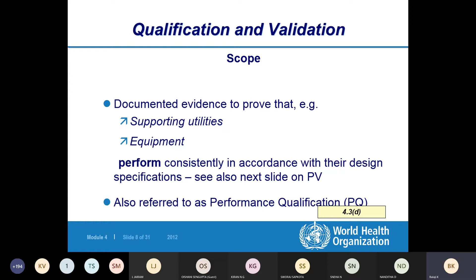Documented evidence to prove that a specific process will consistently produce a product meeting its determined specification and quality attributes is also referred to as process validation. As I told, individual equipment validation is equipment validation separately. So a complete process qualification we also call process validation, because all areas are ready, analysts and operators are ready after qualification, because even the operators should have SOP training and other qualification ready for the process, right? So the operator is ready, the area is ready, the equipment is ready, and all other utilities like compressed air or nitrogen or area temperature and RH, everything is kept ready.